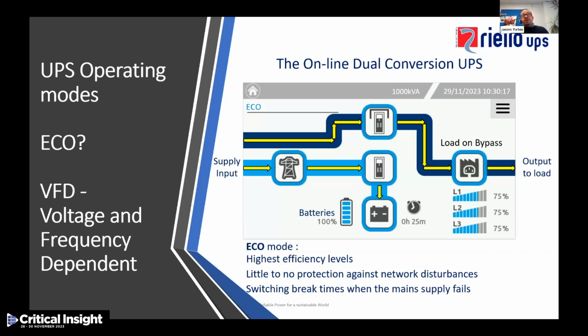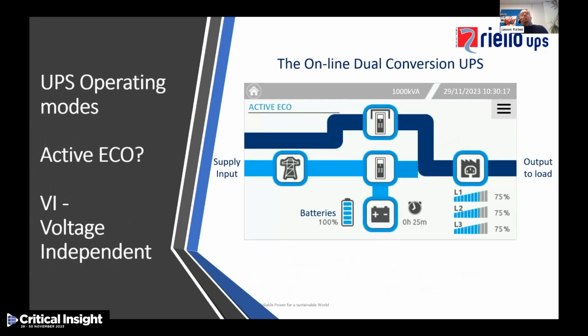The downside to eco mode is that it provides little to no protection against network disturbances, because effectively the load is connected directly to the input. And also, when there is a mains supply failure, there are switching breaks. As it takes time for the UPS system to come online, there is traditionally a small break in power to the critical load. So again, it's not a favored mode of operation. We do have an operational mode that sits in between eco mode and the online mode, and this is active eco. Some manufacturers will give it all different kinds of fancy titles, but we refer to it as active eco.